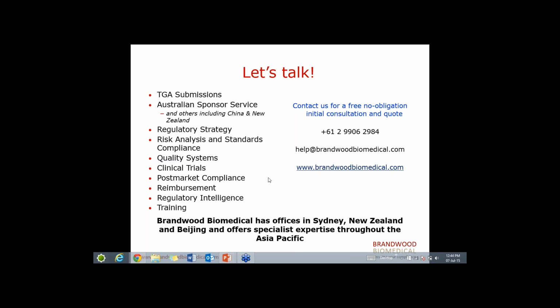Okay, there's a question on how do we know if the device will require an application audit? For classes that are class 1, non-sterile, non-measuring, it's basically self-declared. So you submit your device application and usually within an hour you can get an approval. For classes up to Class 2B, TGA selects the application audit randomly, and this is usually based on their current concerns about particular groups or categories of devices. These can change from time to time. Sometimes they could look at a specific keyword, like software. But as I mentioned, it's time to time, and it is a random application audit.